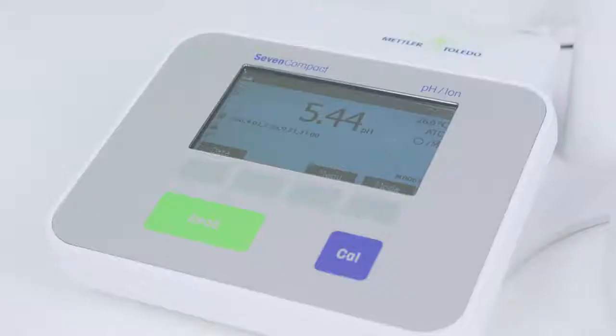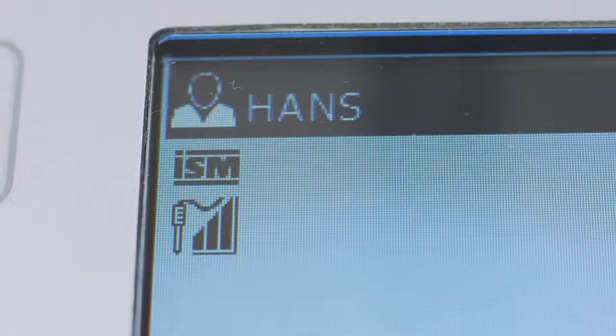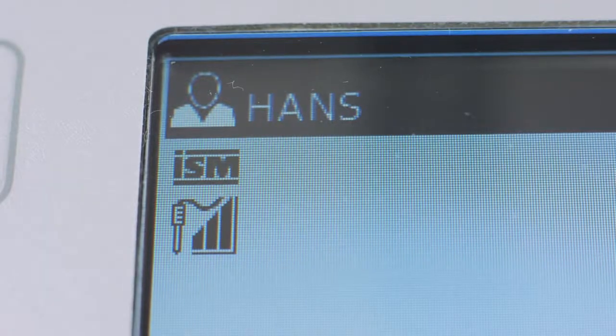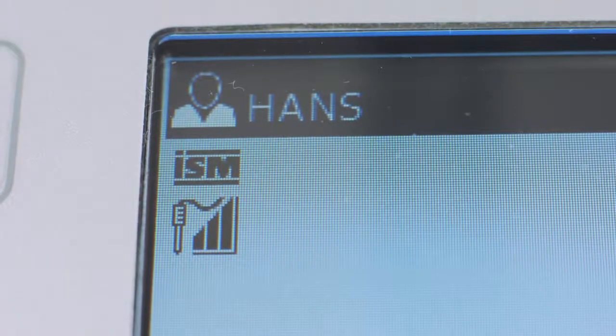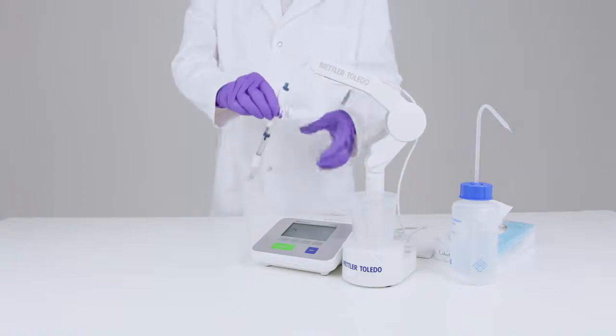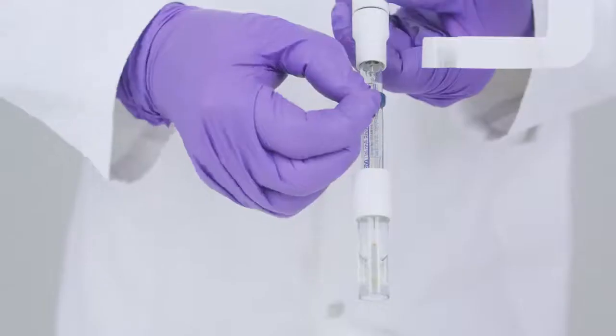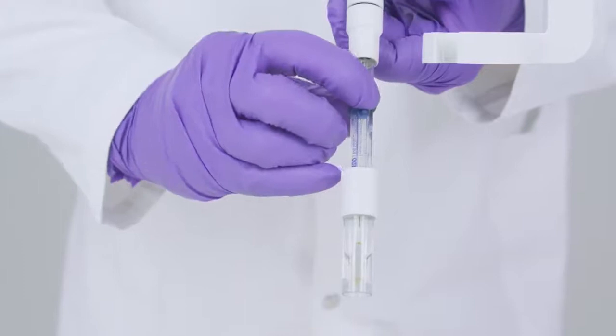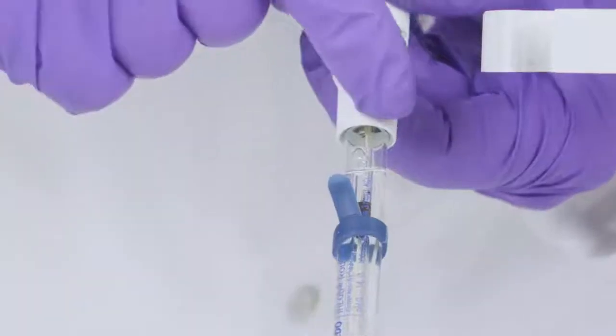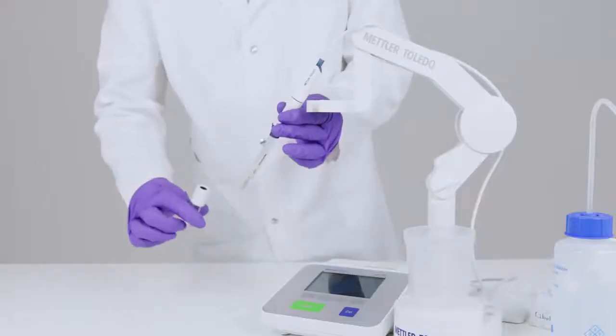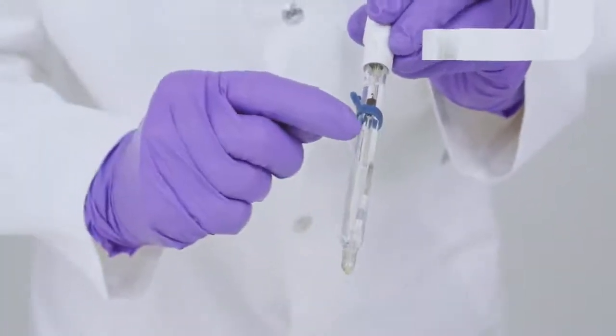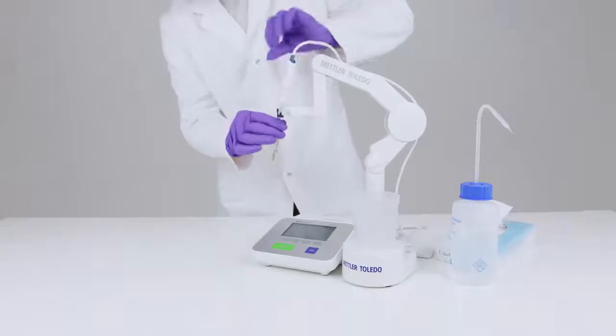If you're using an ISM sensor, the ISM logo will also appear in the display, and the sensor may display a condition icon, which indicates the condition of the sensor and if it needs cleaning or replacing. This icon may not appear till after calibration, depending on when you last calibrated the sensor. If your sensor has a liquid electrolyte, then make sure you open the filling hole before measurement or calibration. Check the electrolyte level, remove the wetting cap, and make sure there are no bubbles inside the lower part of the sensor near the membrane or diaphragm.